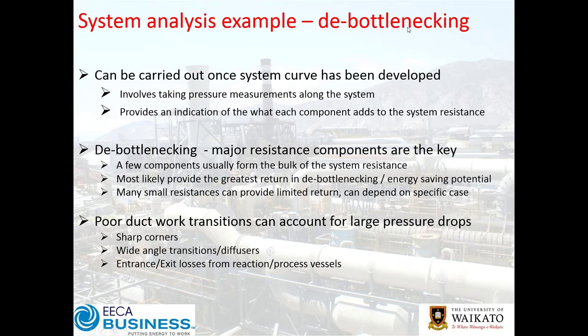For system analysis and de-bottlenecking: once you've got your system curve and pressure measurements along the system, you can see what each component contributes to system resistance. You're looking for the key components that are the major source of resistance — either a few critical components making up the bulk, or the additional system effect resistance from poor duct configuration and interfaces. Generally you get the greatest return on de-bottlenecking by dealing with the big opportunities.